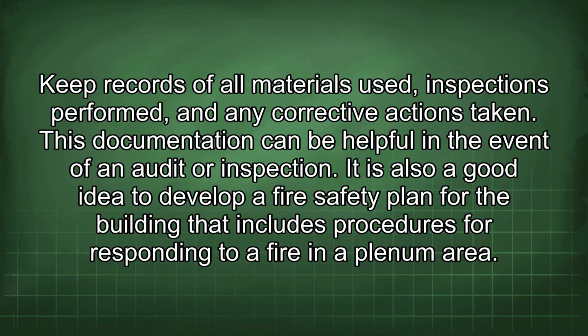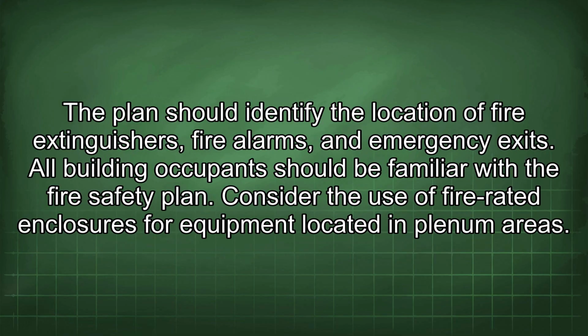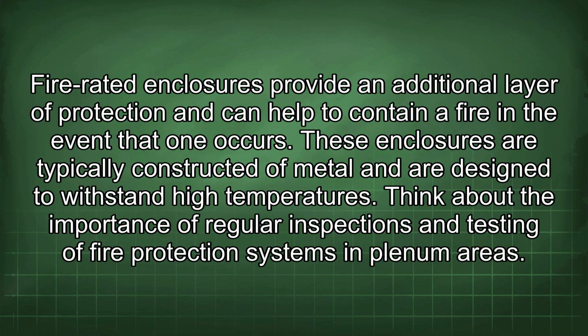It is also a good idea to develop a fire safety plan for the building that includes procedures for responding to a fire in a plenum area. The plan should identify the location of fire extinguishers, fire alarms, and emergency exits. All building occupants should be familiar with the fire safety plan. Consider the use of fire-rated enclosures for equipment located in plenum areas. Fire-rated enclosures provide an additional layer of protection and can help to contain a fire in the event that one occurs. These enclosures are typically constructed of metal and are designed to withstand high temperatures.